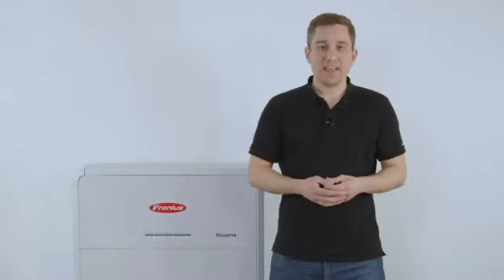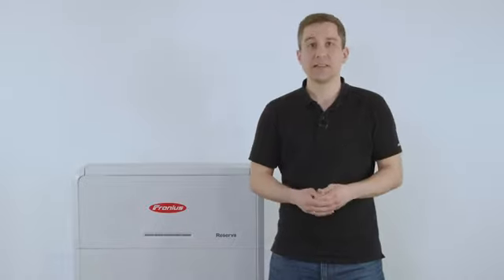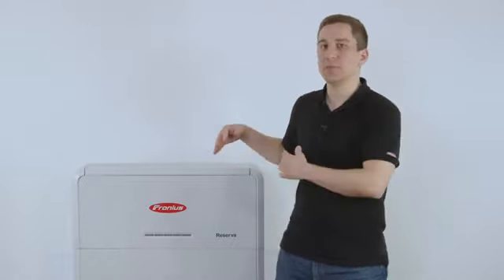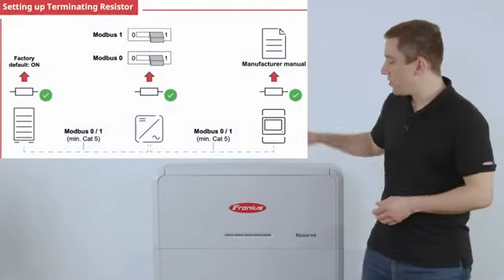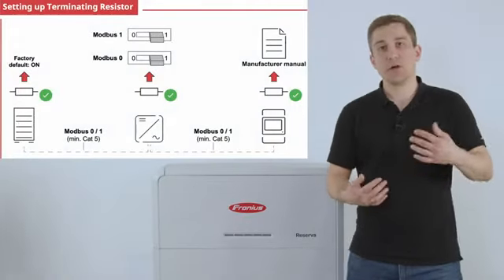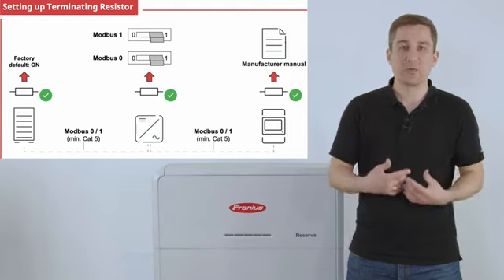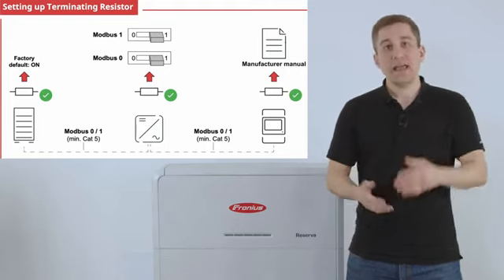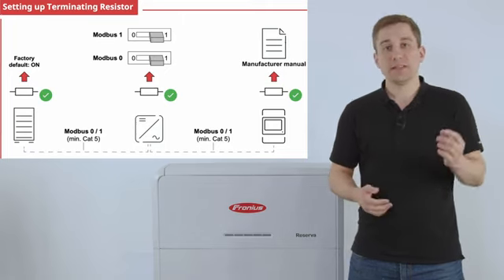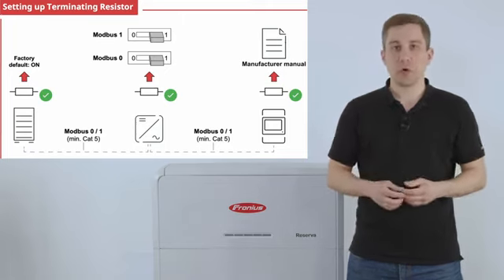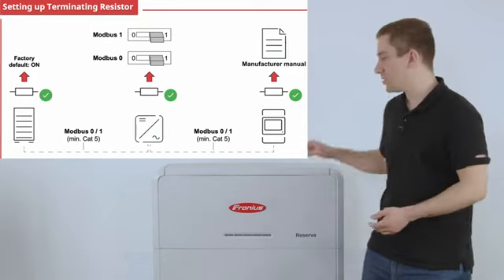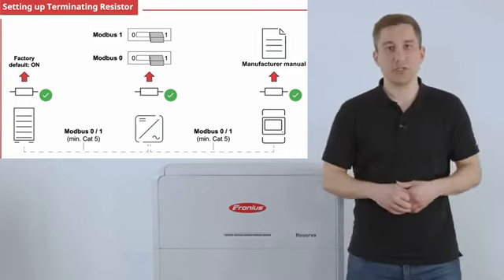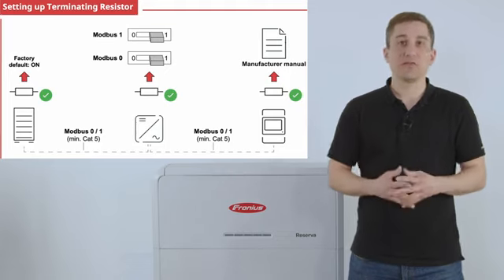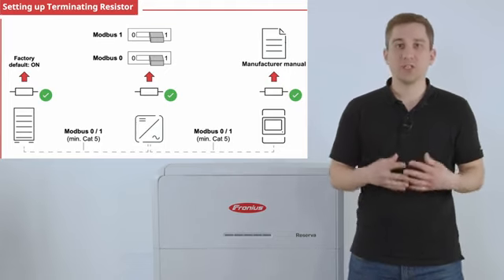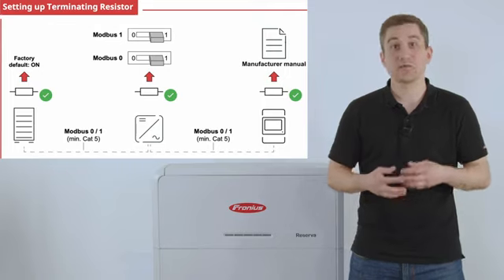Please note, for the data communication, we also need to make sure that for our Modbus communication, the termination resistance is set correctly depending on the setup of the whole system. That means for the Fronius Reserva, the termination resistance 120 ohm is always ex-factory set to on position. For the inverter, you can choose that with our dip switches, so please set the dip switch correctly to on position whenever you install, for example, the Fronius Reserva to the Gen 24 only. Same thing goes for the Fronius smart meter, so depending on the position, please set the termination resistance correctly.